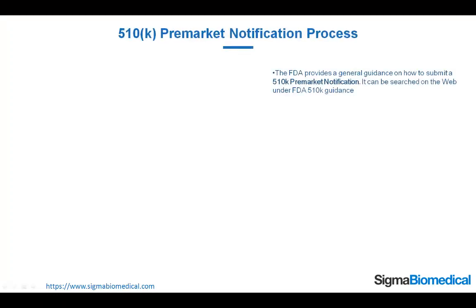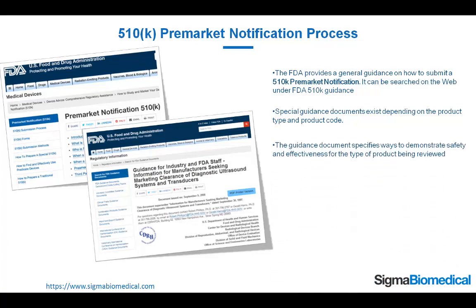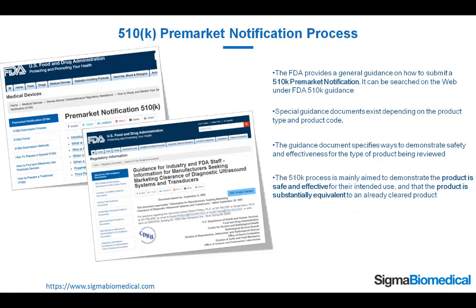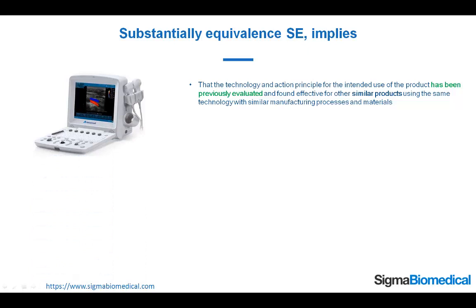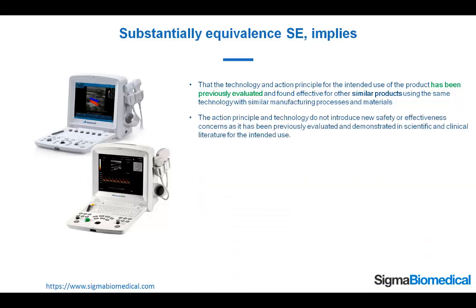510k Pre-Market Notification Process. The FDA provides general guidance on how to submit a 510k premarket notification — it can be searched on the web under 'FDA 510k guidance.' Special guidance documents exist depending on the product type and product code, and they specify ways to demonstrate safety and effectiveness for the type of product being reviewed. The 510k process is mainly aimed to demonstrate the product is safe and effective for their intended use and that the product is substantially equivalent to an already cleared product. Substantially equivalent (SE) implies that the technology and action principle for the intended use of the product has been previously evaluated and found effective for other similar products using the same technology, with similar manufacturing processes and materials. The action principle and technology do not introduce new safety or effectiveness concerns, as has been previously evaluated and demonstrated in scientific and clinical literature for the intended use.